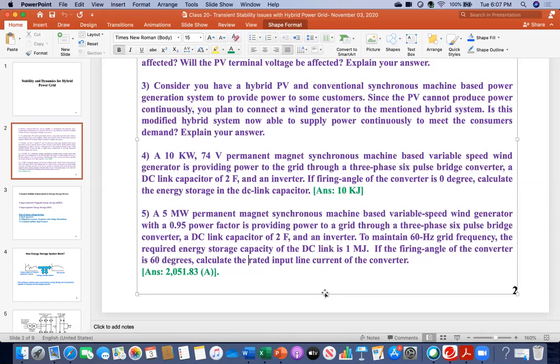I'm using 1.7. Oh no, it is 1.732 minimum, you need to use that number. If you divide with a bigger number at the denominator, like 1.732 or something, then your value will be reduced. I mean a close answer is okay, 2051, 52, or 48, 49, those are okay because of rounding issues. But if it is too much deviated, like 80 ampere, 70 ampere difference, that is too much.